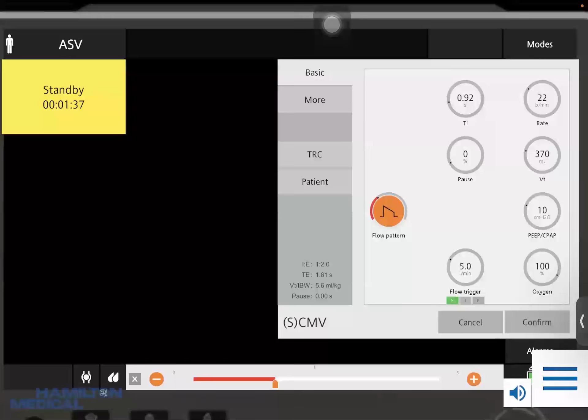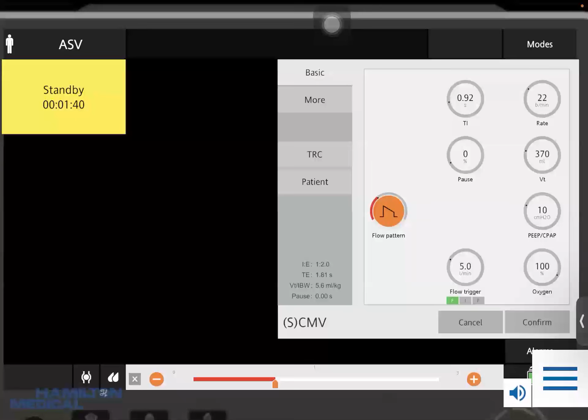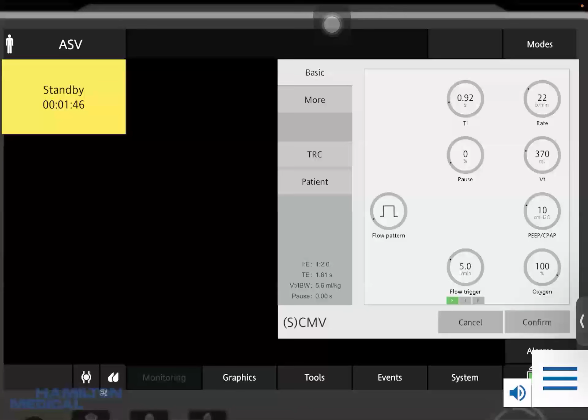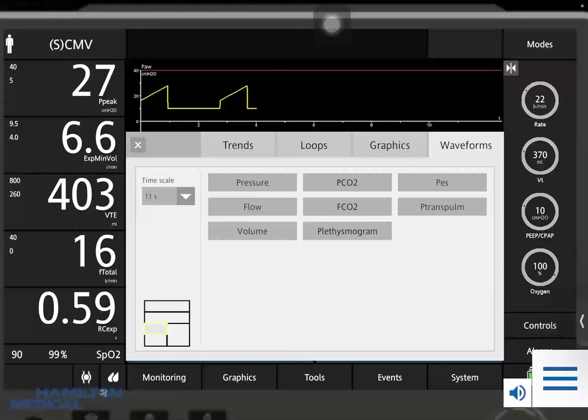Let's see, 370, set. He has been breathing with a high respiratory rate, so this can't be 12. It should be at least 20 to 24. Always remember, when we adjust the respiratory rate, we have to adjust the inspiratory time to set the desired I:E ratio. Here I would set an I:E ratio of 1 to 2. This is a better flow pattern, so I use the conventional one. Flow trigger is the default value. We confirm the patient settings and start the ventilation. Let's see what happens.